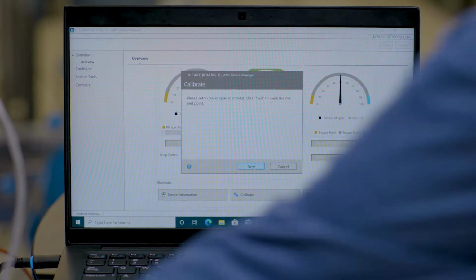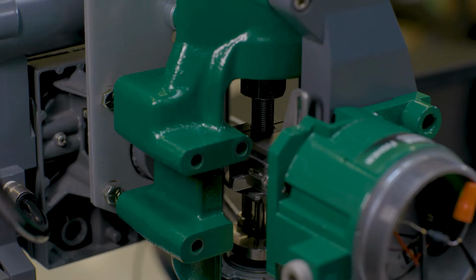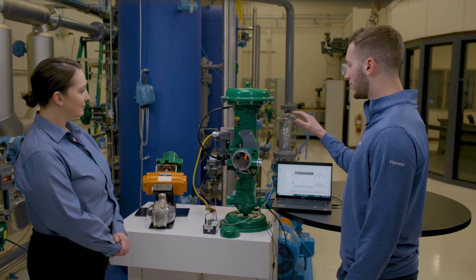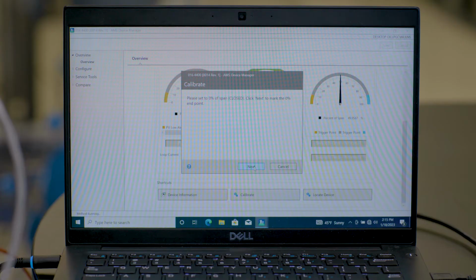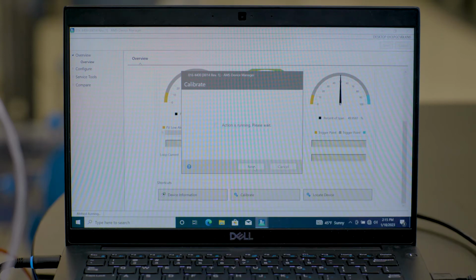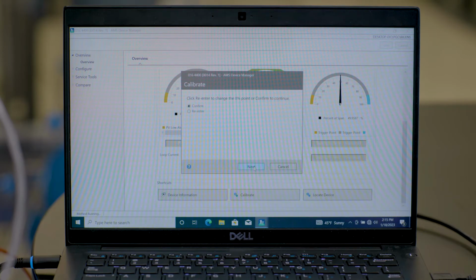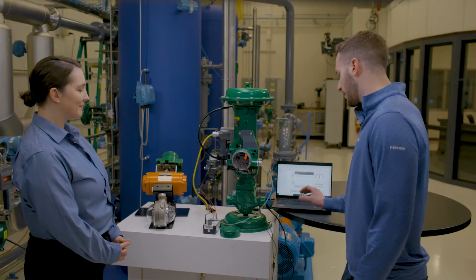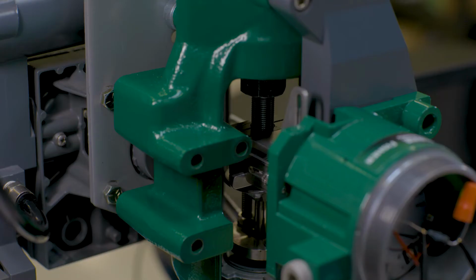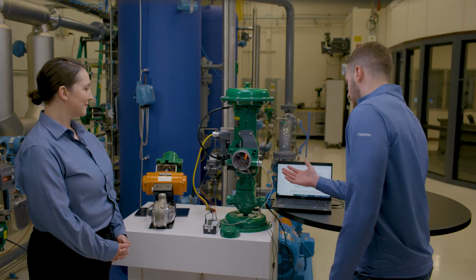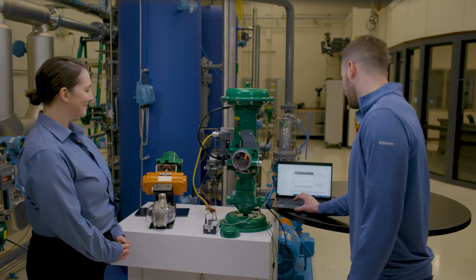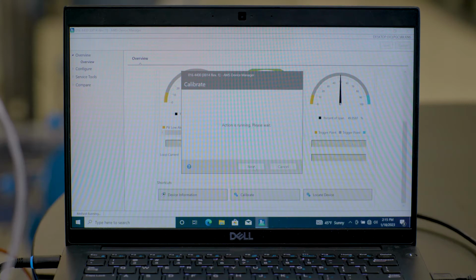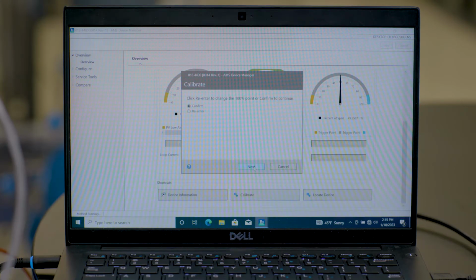Right now I'm going to move the valve fully closed and ensure all of the air is exhausted, then ensure it's fully closed visually and with your gauges, and hit next and confirm. Then I'll move it to the 100% position, again ensure that it's fully up, hit stop, hit next, and then confirm. Then you can accept the new calibration.